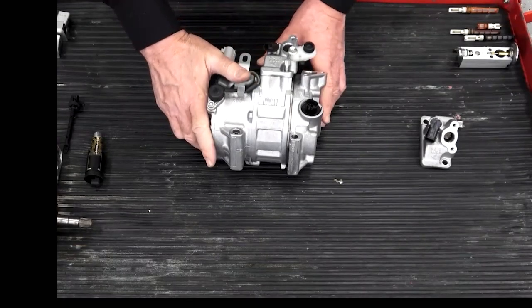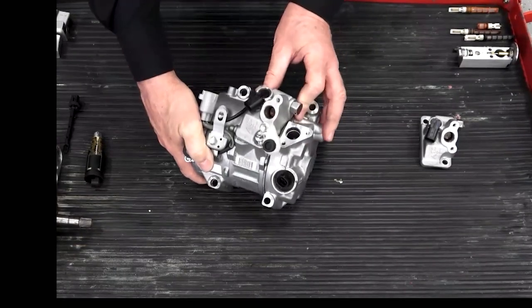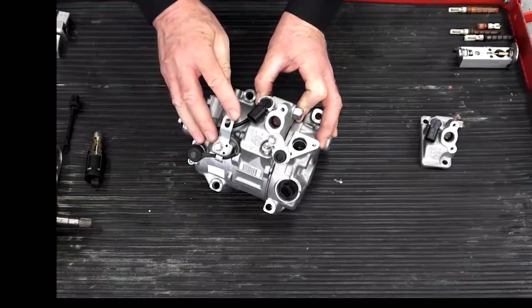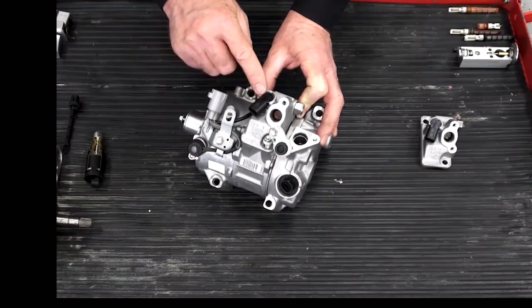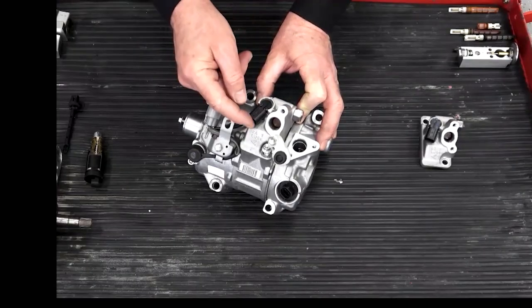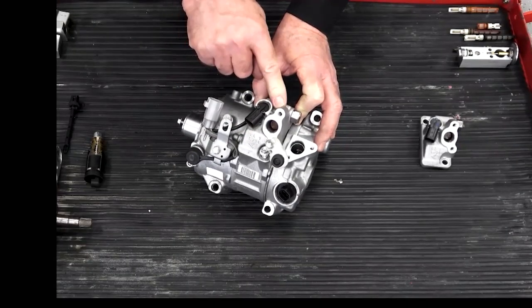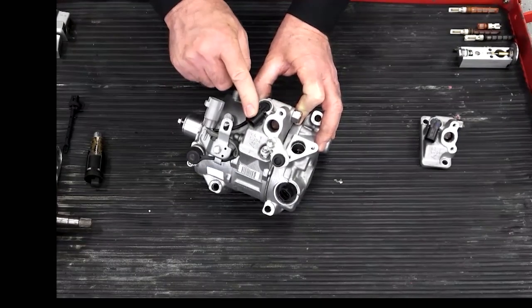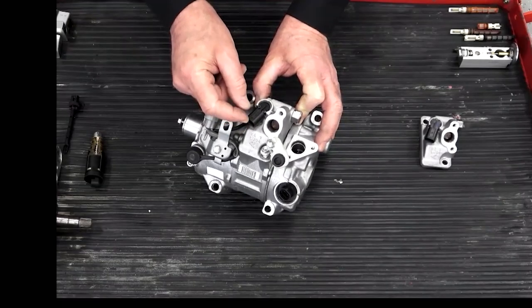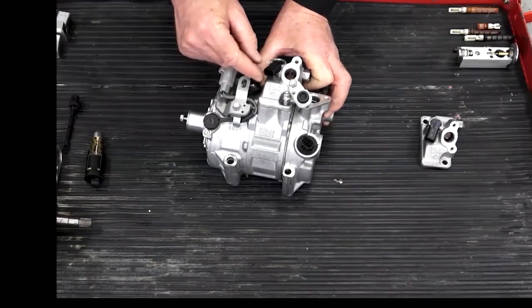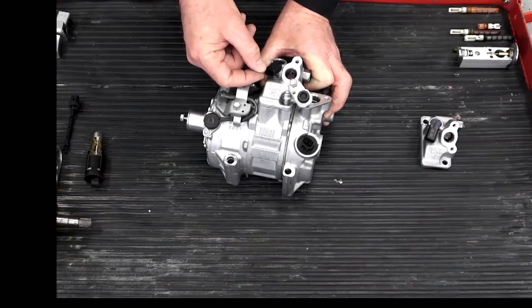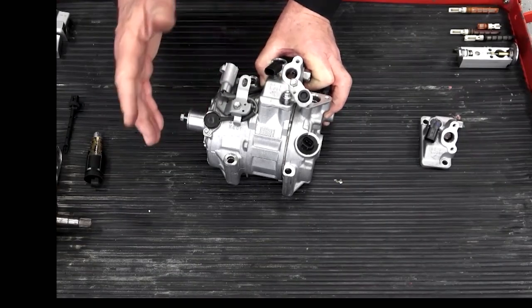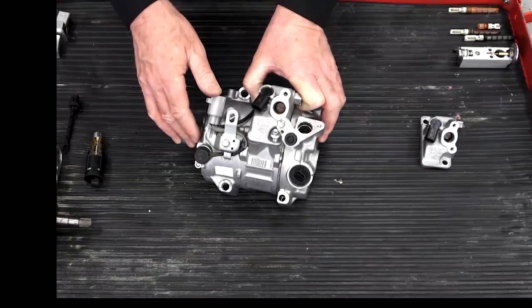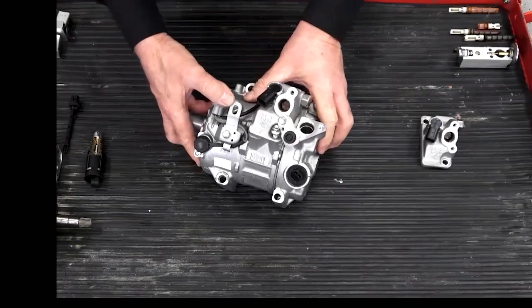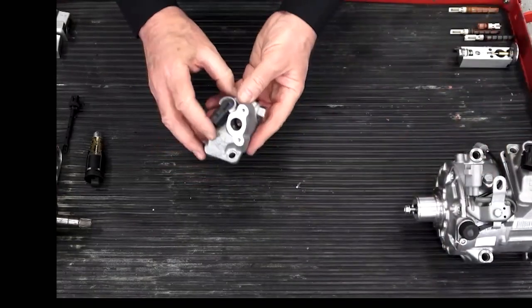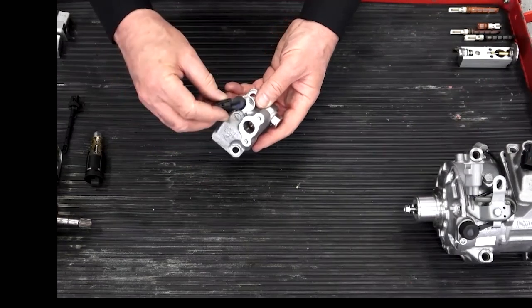The real new technology here that you may not have seen before is if you look on the discharge port of this compressor. You see here there's a sensor. It's got a snap ring holding it to the discharge manifold here. This is what we call a refrigerant volume flow sensor. And again, it's a Hall effect type sensor. It's got a 5-volt reference, a ground, and a signal, just like many 3-wire type sensors. I've actually got one manifold taken off here. The sensor is just held on with a snap ring.